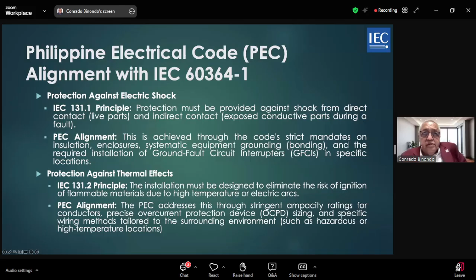Protection against overcurrent: the principle of IEC is that persons and property must be protected against injury or damage due to excessive temperatures or electromagnetic stress caused by overload or short circuit. Mostly, what this protects are the conductors, and it's the same with PEC. The overcurrent protection is intended to protect the conductors in the installation, so conductors or equipment don't sustain damage.